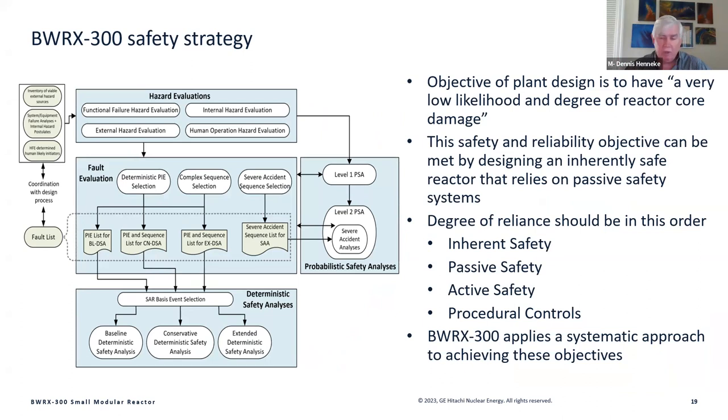This is, believe it or not, the simplified version of our fault evaluation or safety strategy that implements what I've described. And what you have are the hazard evaluations. Unfortunately, under IAEA terms, something that would be an internal event, like a LOCA, is still called a hazard, or a loss of feedwater event is still called a hazard. All these hazard events go through a deterministic evaluation and a probabilistic evaluation in order to develop input to the fault list or the postulated initiating event development. Now, postulated initiating events are not just those simple events like a loss of offsite power or loss of feedwater event.